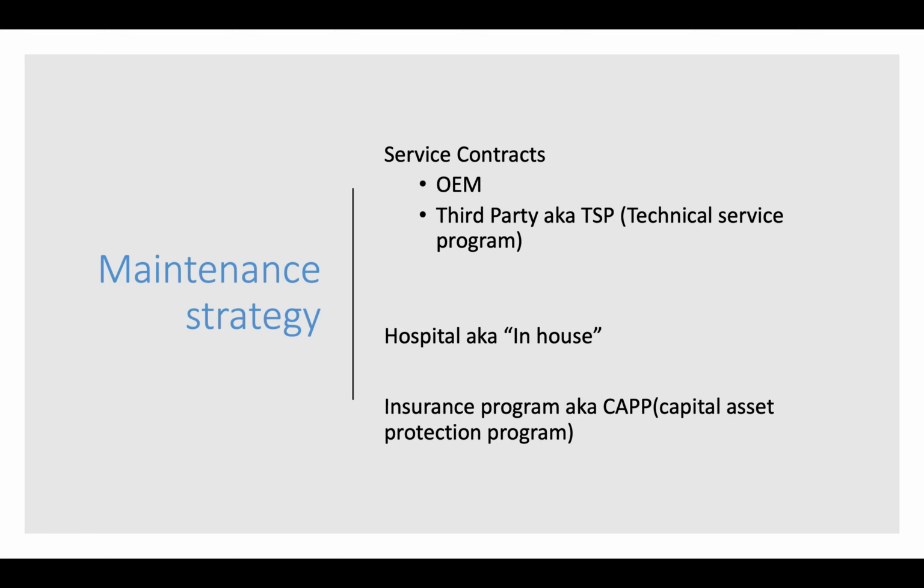One thing to note is not every facility is going to choose to handle every device. Many hospitals don't really have the capacity to handle the tens of thousands of devices that they may have in their system. So they can often hire an OEM or a third party to do the service for that device, especially a lot of times high-end devices, maybe x-ray equipment or anesthesia equipment. It's a little more technical. They'll have a service contract on that so that they don't have to keep all their employees up to date on certifications for those particular devices, which can be very expensive.